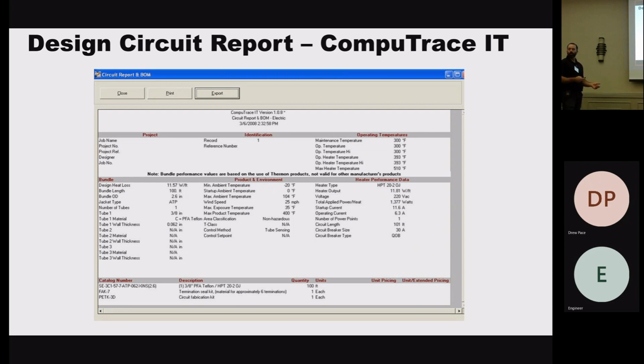Any bundle operating at those temperatures on a stack, they're not going to be T3, I don't care what they say. The plant might be T3, but that stack can be exempt because the exhaust gas is way too high. So they normally exempt that stack out of that area classification. We know that in the US, but we're fighting it in the Middle East right now where stack temperatures are high and they're telling us it's a T rating, and we're like, no, there's no way you can do that. It's just not possible.